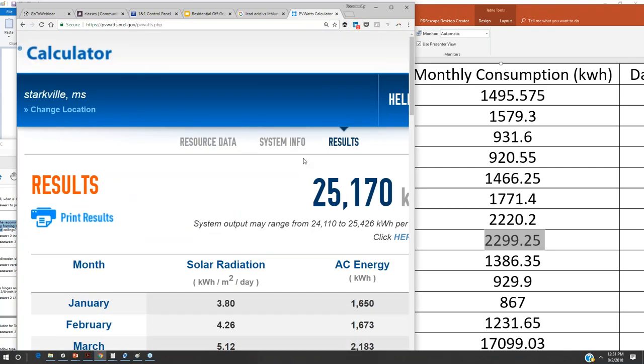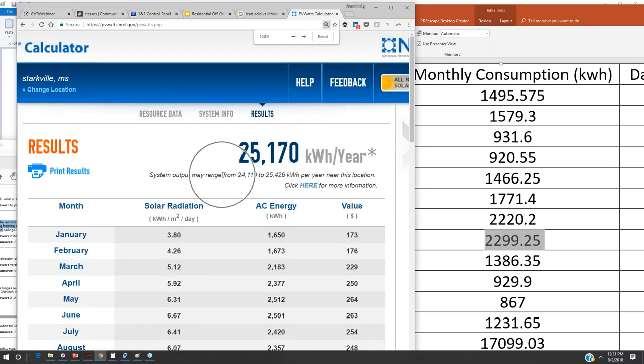So it actually looks like my 18 kilowatt solar array is a little bit oversized, except that would be assuming that my daily average consumption is equal to my daily average production. And that's not true. I mean, you've got your weather systems coming in. And so in the wintertime, I'm going to have sunny days and I'm going to have overcast days, but I have to take into account the overcast days.